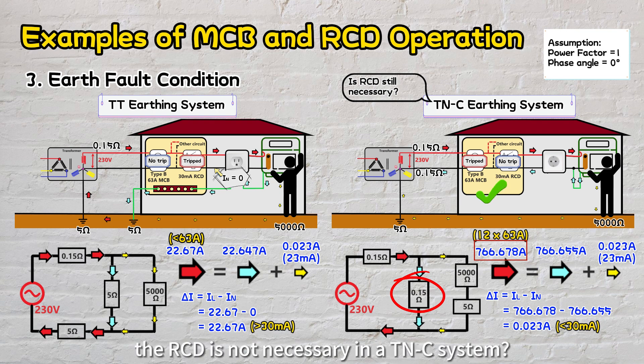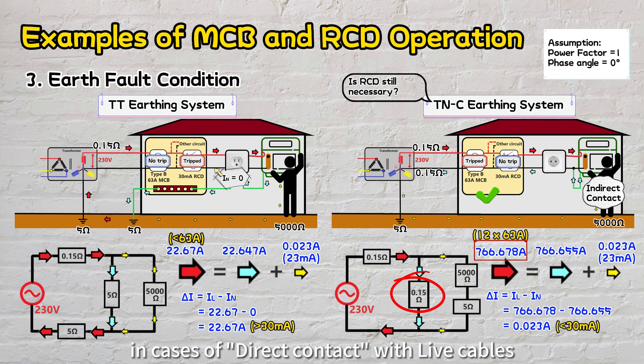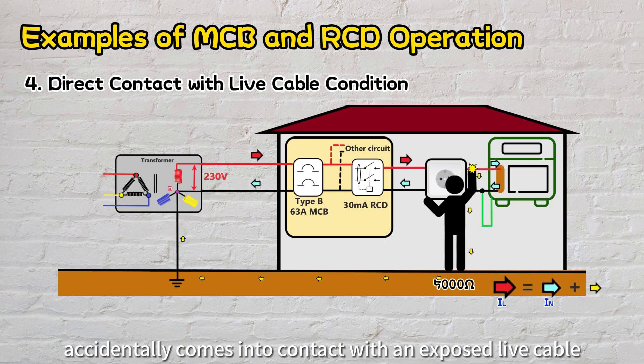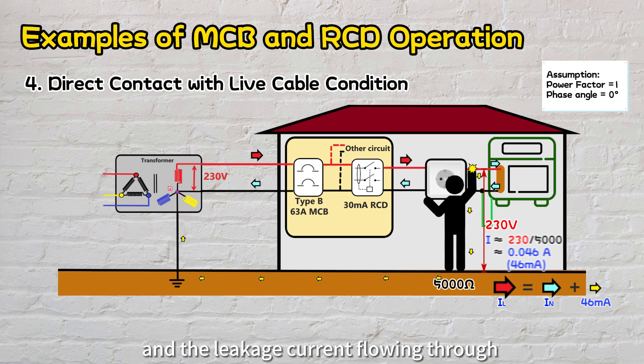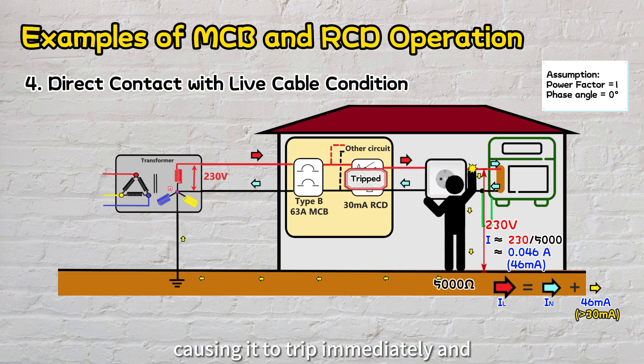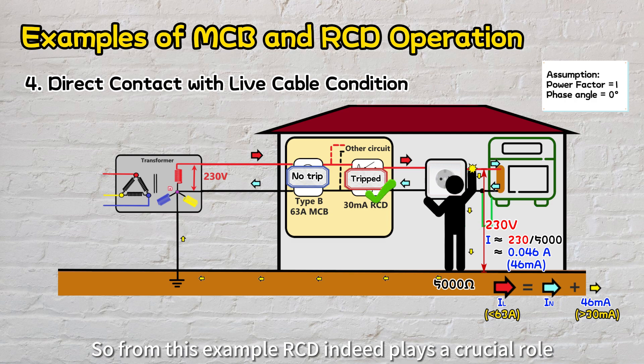Does this imply that the RCD is not necessary in a TNC system? In fact, the previous scenario considered indirect contact with equipment frames. In cases of direct contact with live cables, MCBs cannot provide any protection. So in the fourth scenario, let's consider a situation in a TNC system where a person with a body impedance of 5,000 ohms accidentally comes into contact with an exposed live cable. The voltage across the person will be approximately 230 volts, and the leakage current flowing through the body would be approximately 46 milliamps. Consequently, the difference in currents exceeds the 30 milliamps sensitivity threshold of the RCD, causing it to trip immediately and effectively reduce the risk of electric shock. Due to the small current, the MCB would not trip during direct contact with the live cable. So from this example, RCD indeed plays a crucial role.